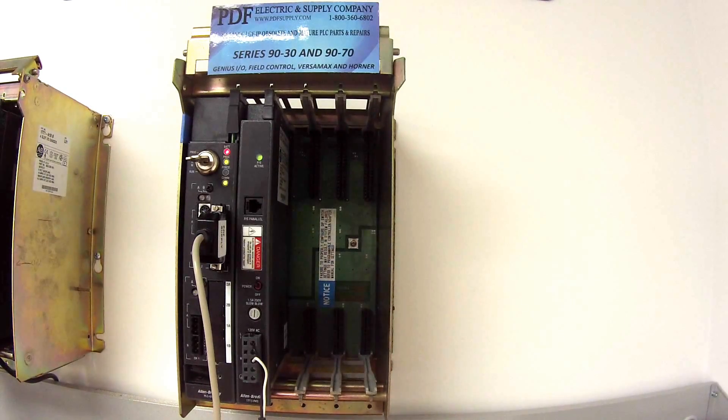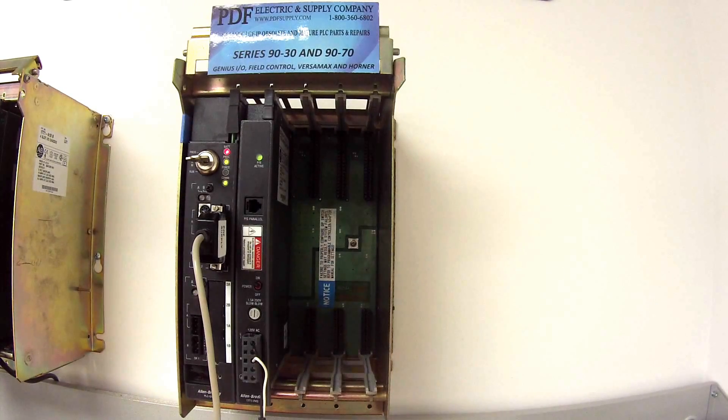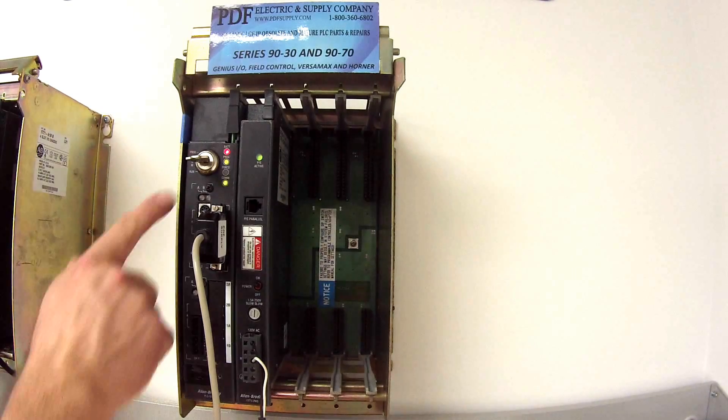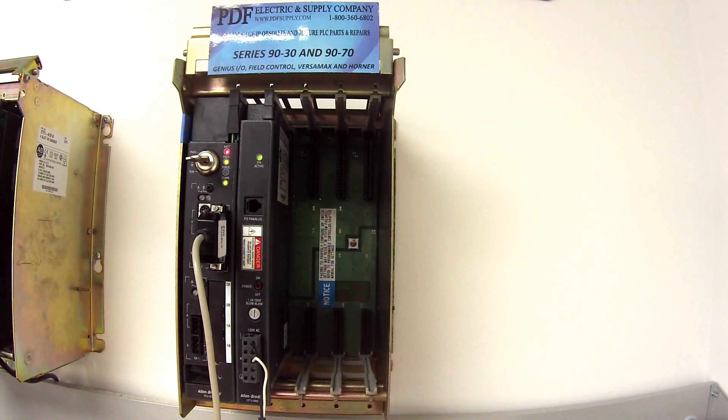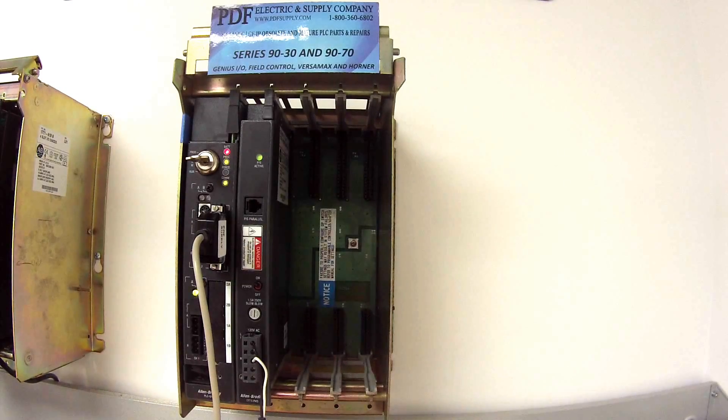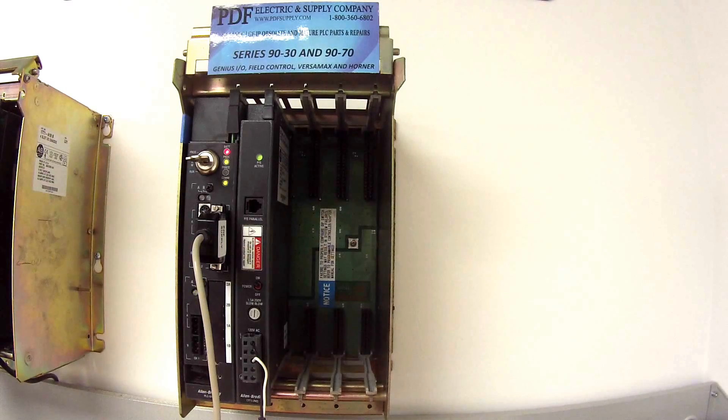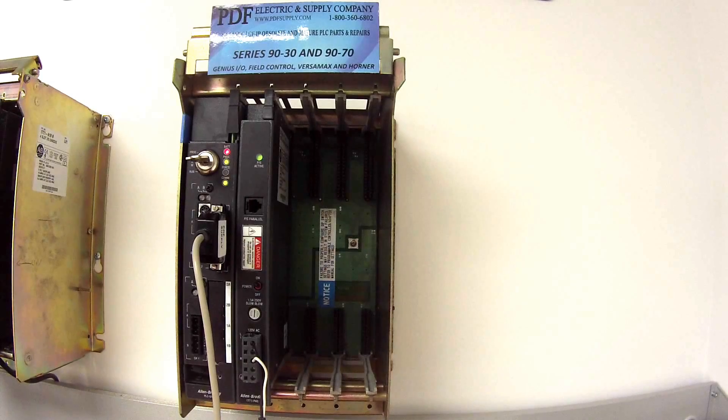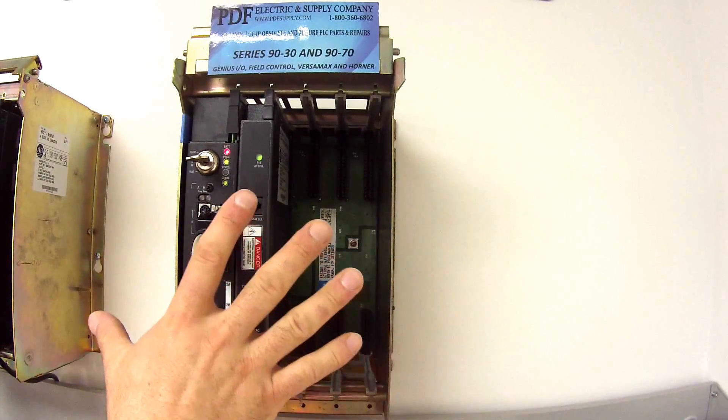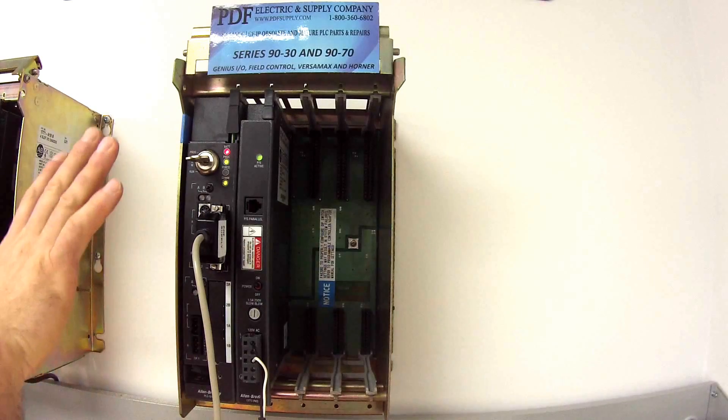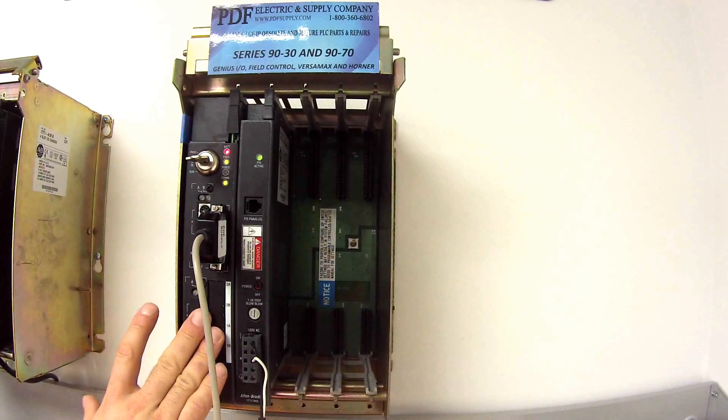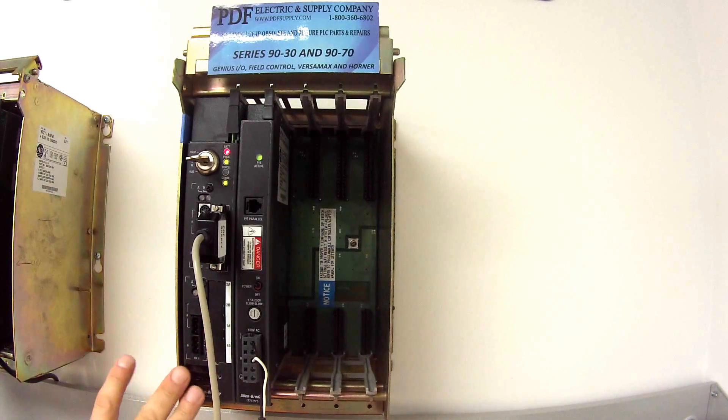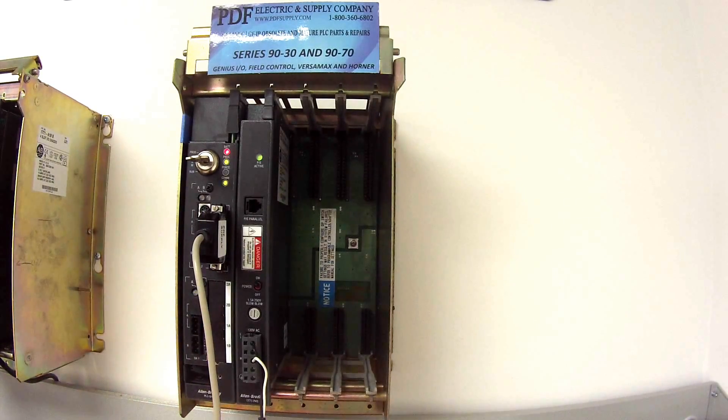So if I don't see anything major, next thing that I might do is leave the processor in run mode, remote run, like you see here. It doesn't have to be in hard run for the test that we're doing. And we want to see that the processor is able to sustain itself in run mode for a couple days, two or three days, maybe over a weekend. You could put other modules next to it. You could create a situation where it's hotter by blocking off the airflow a little bit to maybe put it under load a little and see that it's able to sustain.